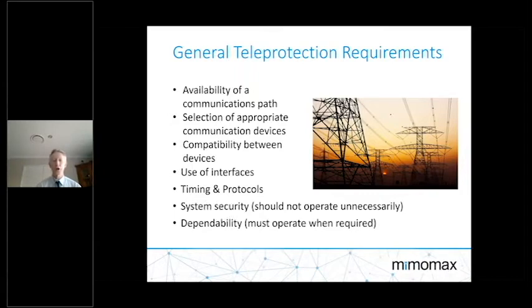System security, which means that the operation should not operate unnecessarily. So ensuring that the probability of getting a false trigger through some form of interference or other impacting signal is minimized, and dependability makes sure that it must operate when it's required. So ensuring that the operation is dependable and highly reliable. And these metrics come from a number of standards that have been produced, but one of the key standards is 60834-1, that's an IEC standard, and that is related to teleprotection equipment for power systems. So haven't got it listed there, but just to remind you of that standard, that is IEC 60834, and that relates to teleprotection equipment for power systems. So both latency, system security, dependability become a big part of designing that network.